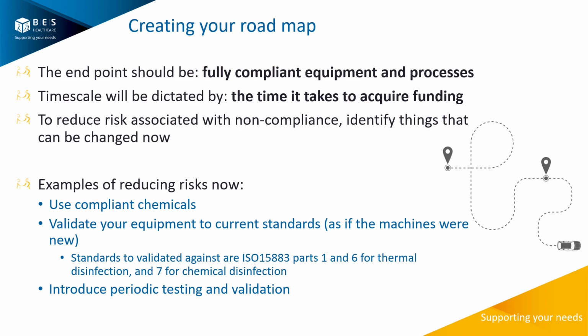That would at least be one step better than using non-compliant chemicals in a non-compliant machine. Likewise, you could validate your equipment to current standards, as if they were new, because it may well be that the machines actually perform at the level required, they just don't have the certification for that, and you could get around that by doing some of the certification yourself.